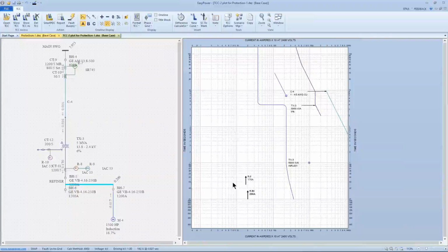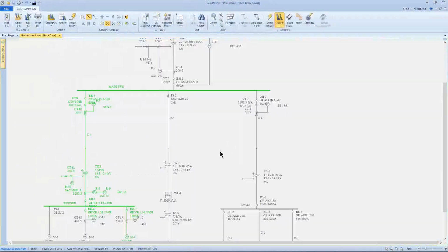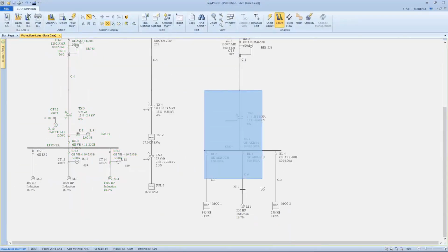Now, relays themselves will show whatever the relay setting is. Normally, relays work with symmetrical current, so this is not that good of an example as it would be if I picked out a breaker. So let's go back and make the comparison with breakers.